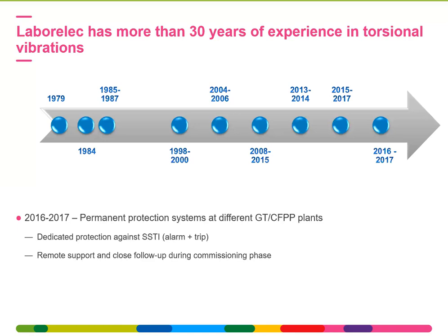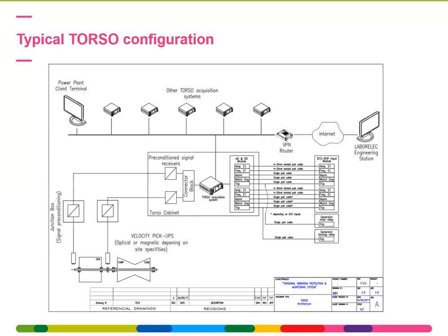Now, these last years in South America, there were some important issues with rotor shaft cracks after 200 to 300 hours after the commissioning of a gas turbine power plant. And this raised the awareness at all the power plants nearby to do the risk assessment. So there we have installed a dedicated protection system against this potential interaction, and also remote support and close follow-up during the commissioning phase of the power plant. So these are examples showing the experience of Laborelec for more than 30 years already.